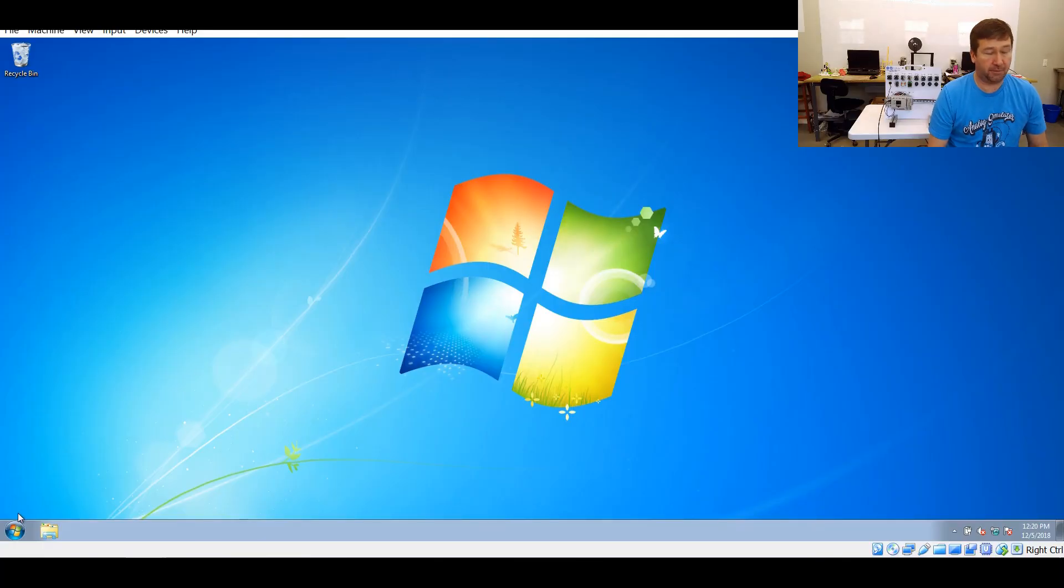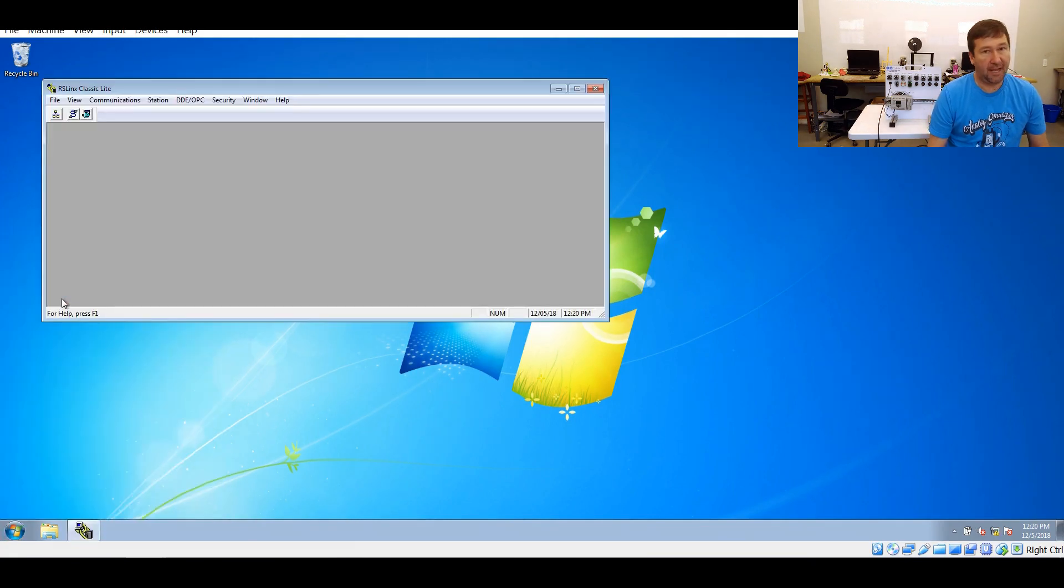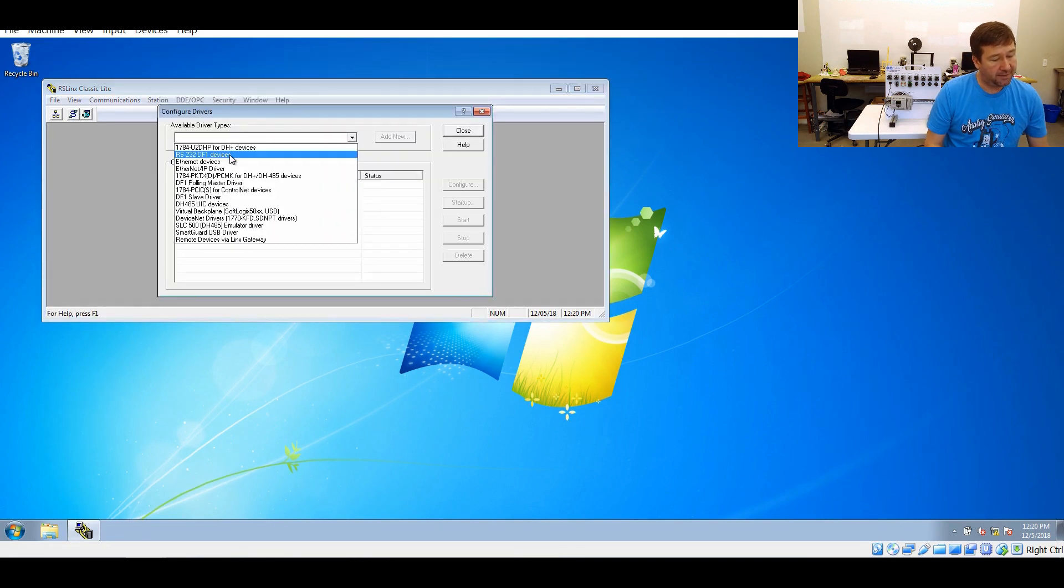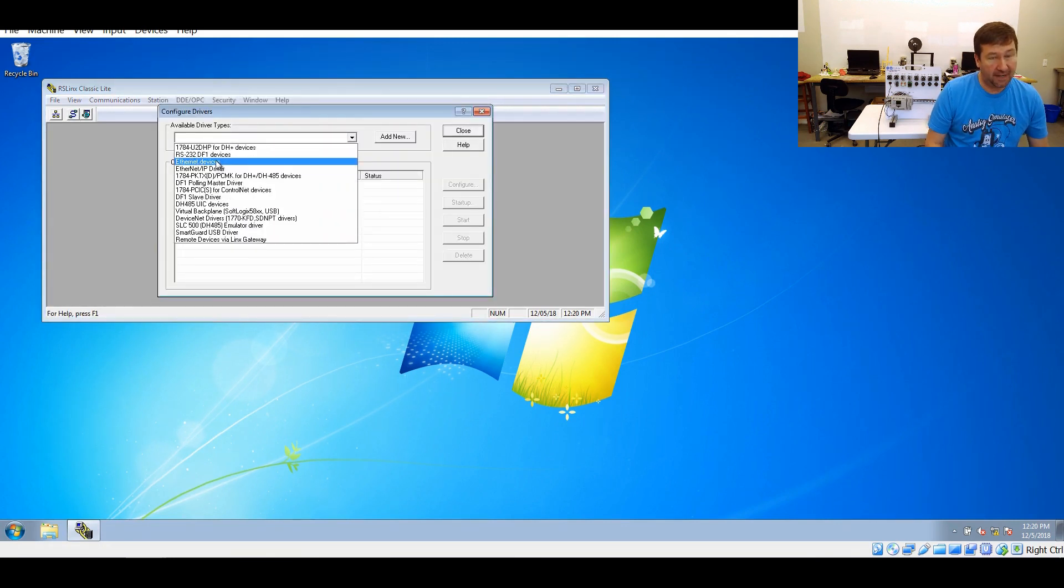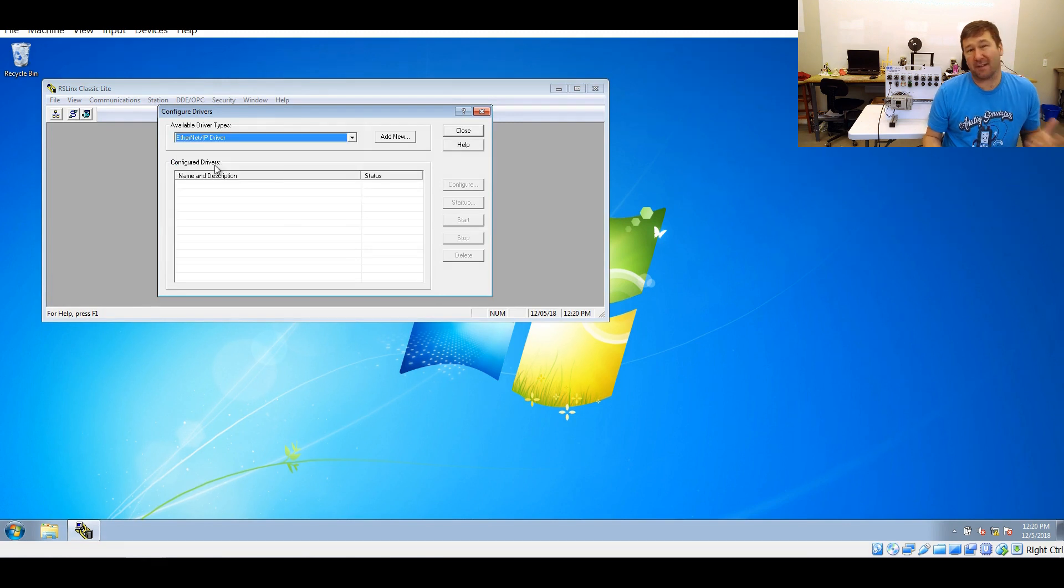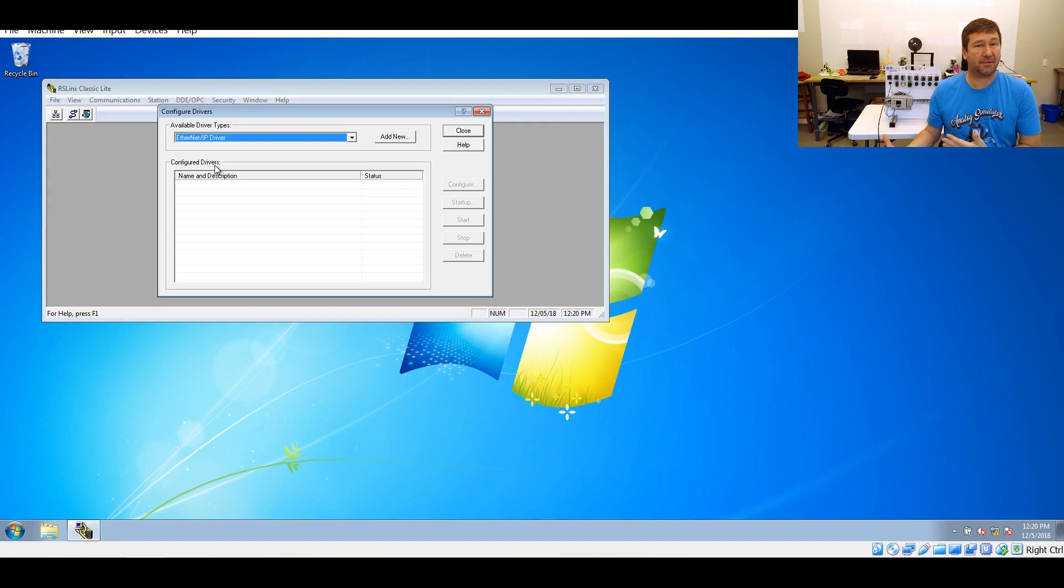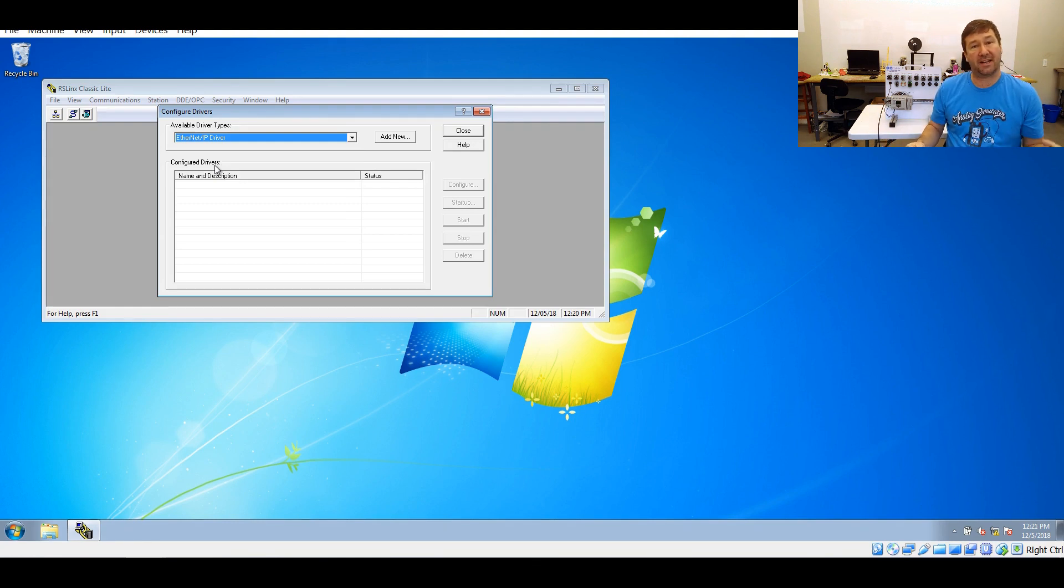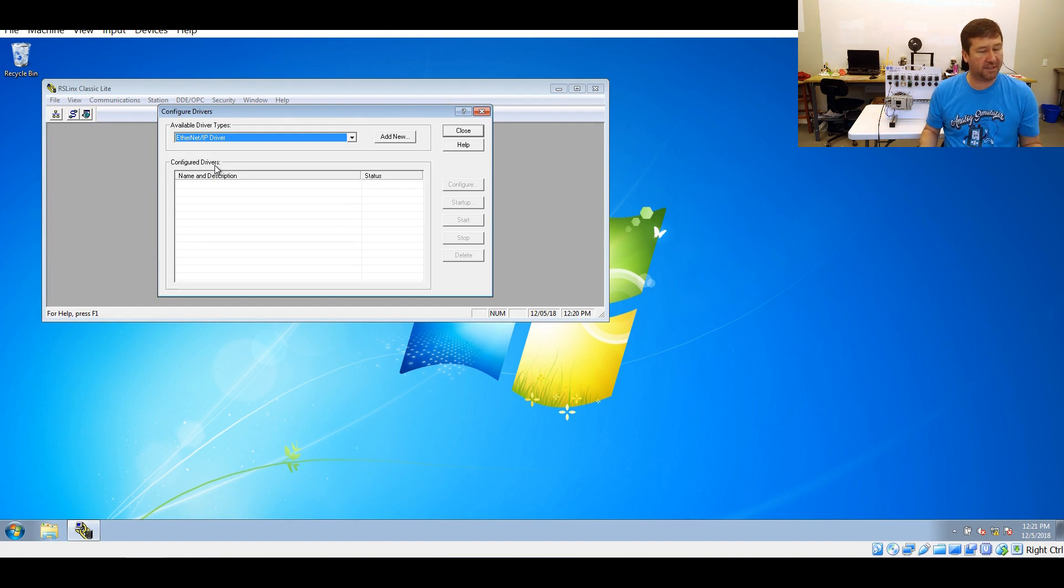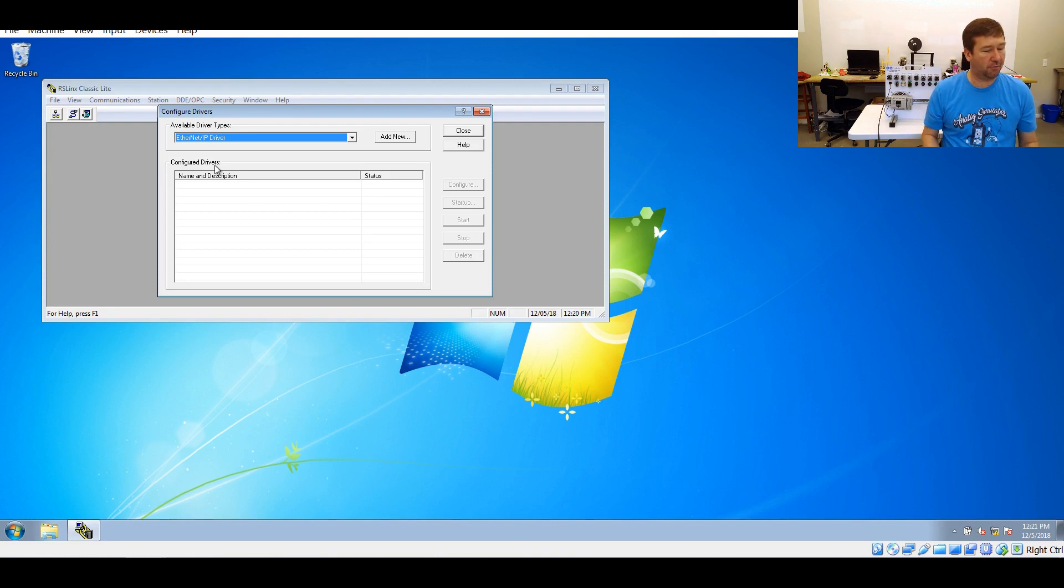Just like with the serial one, we're going to start off in RSLinx. There's two Ethernet drivers that you could actually use. You have the Ethernet devices driver and the Ethernet IP driver. The Ethernet IP driver is slightly easier to configure because you don't actually need to enter your PLC's IP address. You just have to be on the same network. But the broadcast packets that Ethernet IP uses to discover PLCs could get blocked by routers. So if you're having that problem, you may have to use the Ethernet devices driver. We're going to go through both of them here.